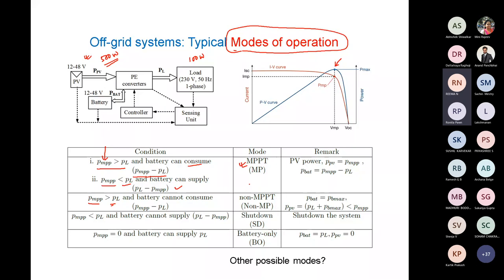So what we'll do is deliberately operate at some other point, not at the MPP point, maybe somewhere here. So actual PV power will be less than PMPP - what I could have generated, I'm generating less than that. This has to equal my load demand plus whatever maximum my battery can consume. Sometimes if the battery is fully charged, then this has to go to zero.